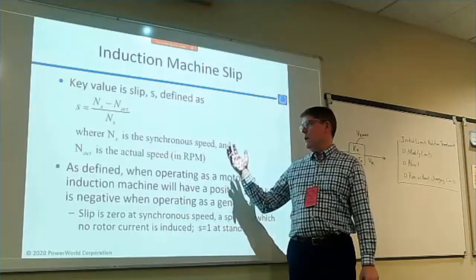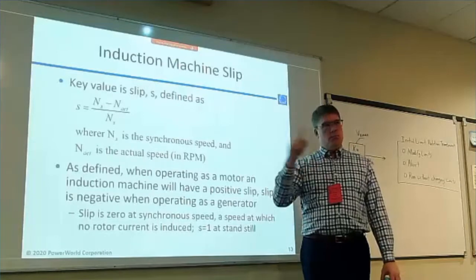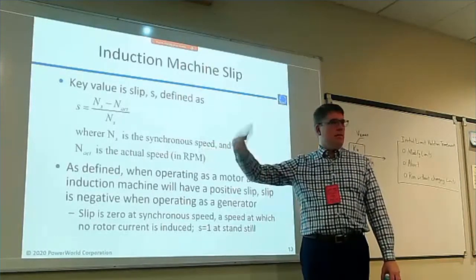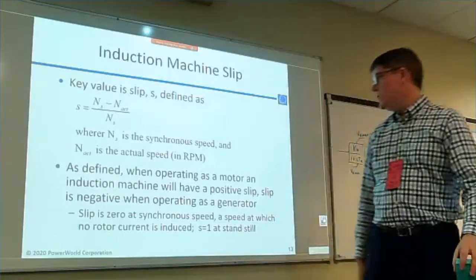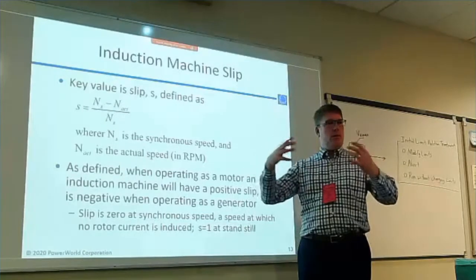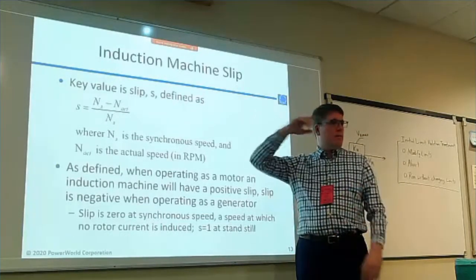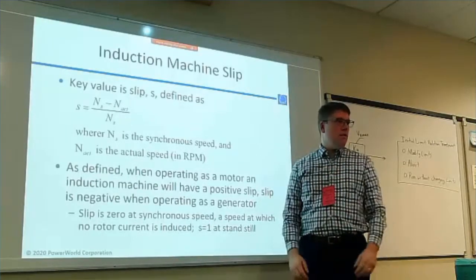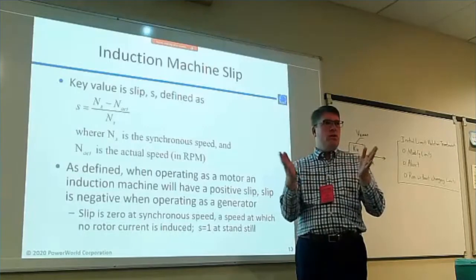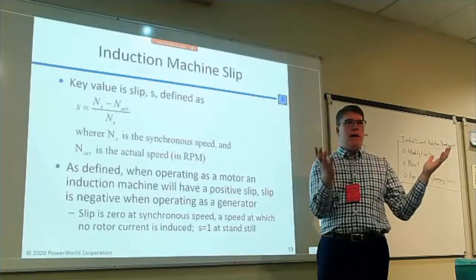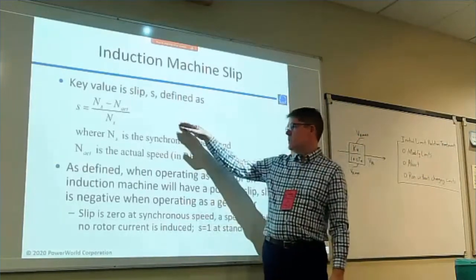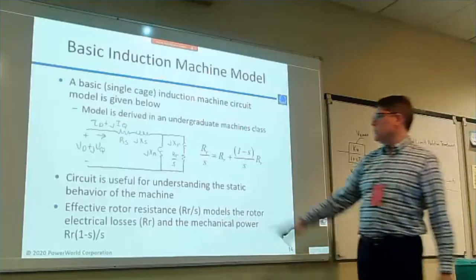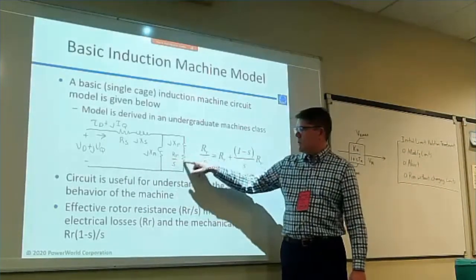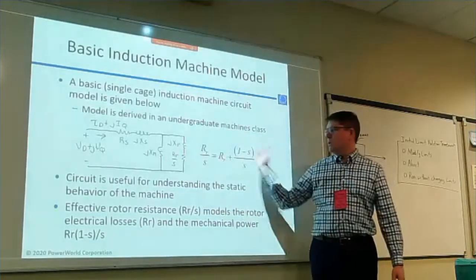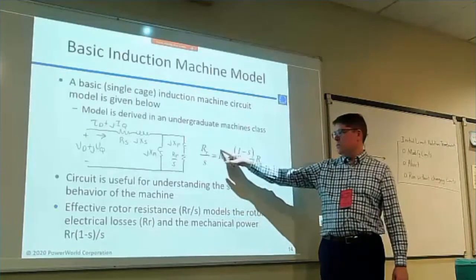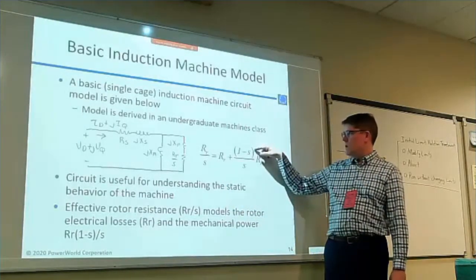Slip is basically the normalized difference between the speed of the rotor and the frequency of the electric signal. Induction motors will always spin slower than the frequency of the electric system—it's like they're trying to catch up the whole time. So if the system's at 1 per unit frequency, an induction motor will be at 0.9-something at steady state; it's always a little behind. These terms always show up as 1 over S. This term on the induction motor, if you go through the derivation, is really two terms: the rotor resistance itself plus 1 minus S.